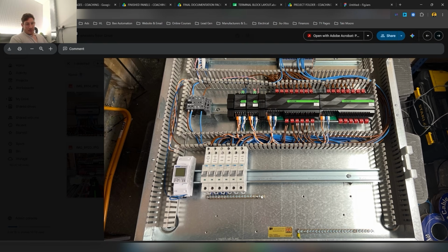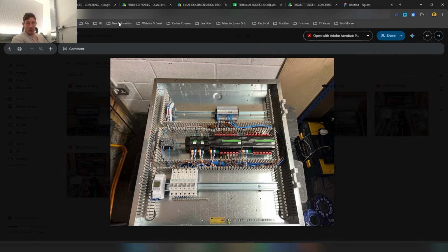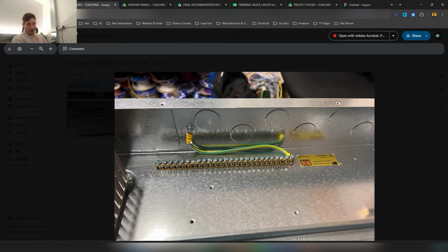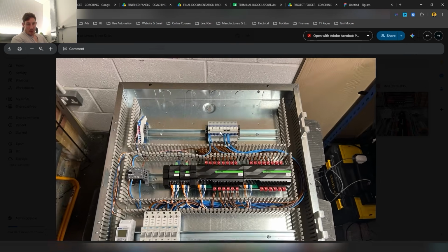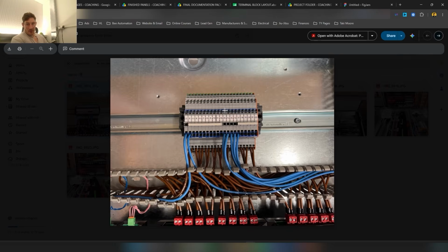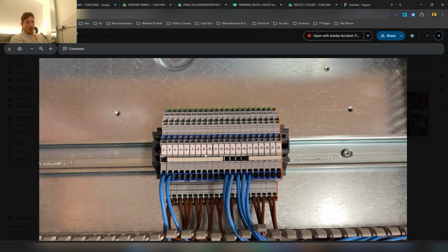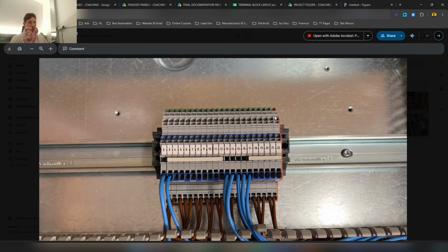Neutral is going to be connected to this bus bar here, the earth's going to be connected here. So we want to make sure we've got a solid connection to the panel as well, because what's happening is all of these terminal blocks - these are 230 volt mains terminal blocks, really nice terminal blocks from Wago. Rather than having three terminal block widths for live, neutral and earth, Wago have done it all in one.